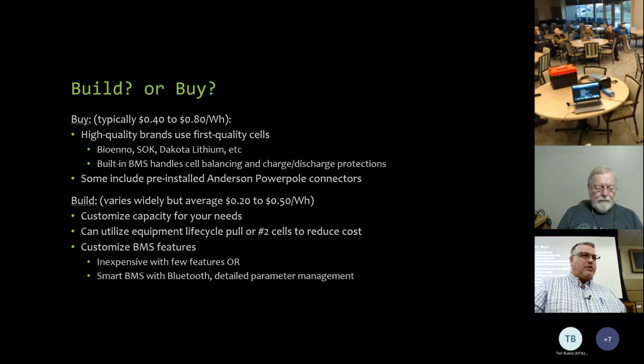You could also make an option to use a number 2 cell. Generally you'll find there's a holographic sticker on it with a QR code, and a lot of times that'll be scuffed or scratched off — the manufacturer's attempted to say, nope, this isn't meeting our standard. But you can buy those pulls knowing you're not going to get the full nameplate capacity out of them, or maybe the full nameplate number of cycles, but they can be a good value if you're looking that way.